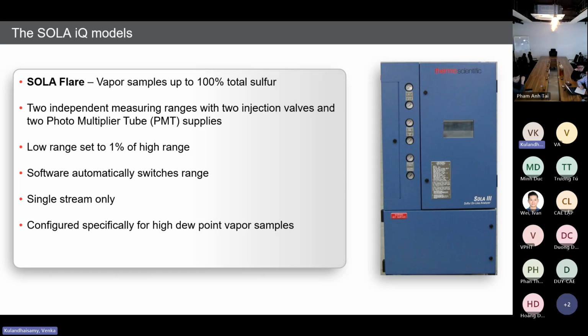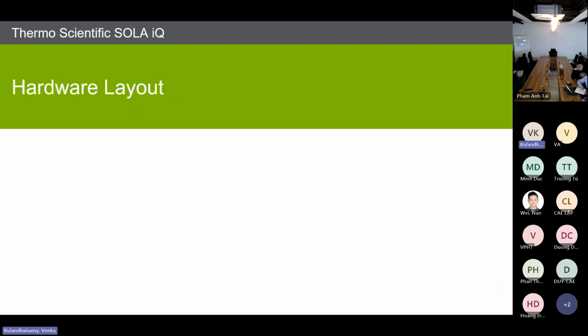But for the flare gas application, we need to use only one stream. The flare gas cannot be used for a multi-stream application because, due to the high sulfur range, multi-stream application is not very reliable. That's why we go for a single stream for the flare gas application. So that's all about the models of the SOLA IQ.